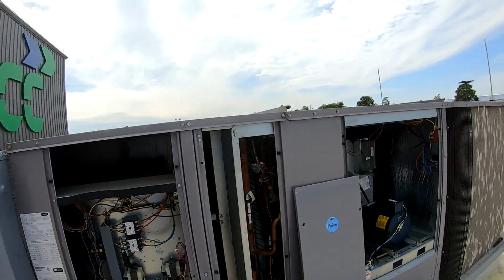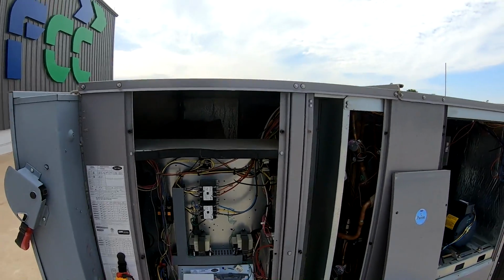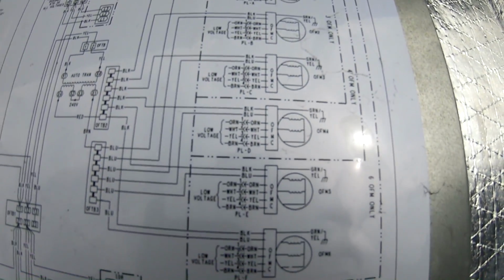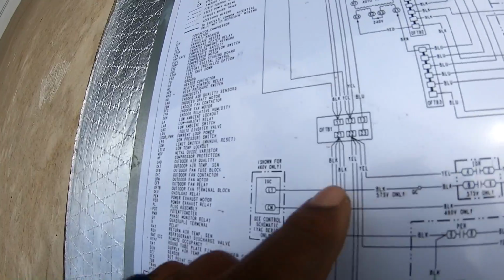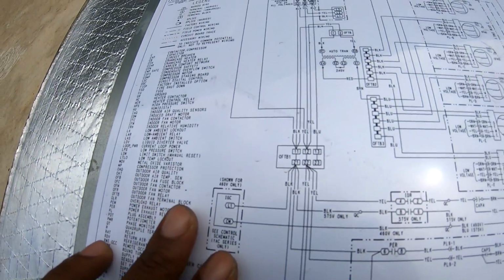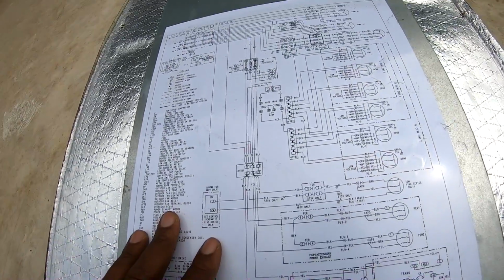I don't see any capacitor in anything, and it is 3 phase. All right, so these are my outdoor fans, which are ECM motors, because you see they got low voltage connections to them. So I just go over here to the outdoor fan, and this is pretty much all hooked up to it. So I have an outdoor fan fuse block, an OFB, an OFC, outdoor fan contactor, and then the outdoor fan motor, outdoor fan relay, and the outdoor fan terminal block. So I'm gonna locate all those within the system, check those fuses that go into the fan, check the relay, and troubleshoot it that way and see what's going on.